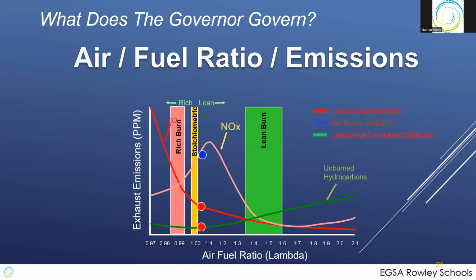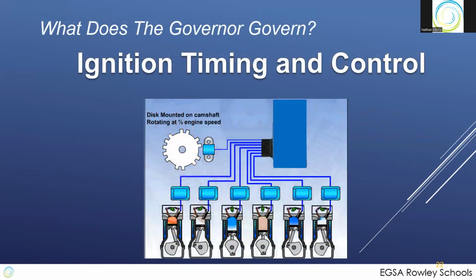It also handles the air-fuel ratio mixture for gaseous engines. You want to control and reduce your hydrocarbons. So there are stoichiometric points on the curve where you want to maintain emissions. So the governor controls the emissions, if you will, or the fuel ratio in order to get the right emissions. It does timing. If you're on a spark engine it controls the spark, or if it's an injector, it controls when the injectors inject fuel into the cylinders, but it's all done by the governor function, right?